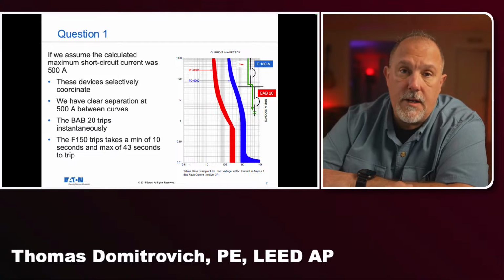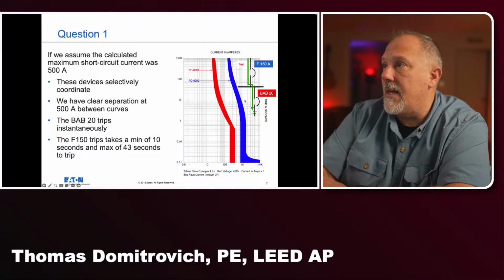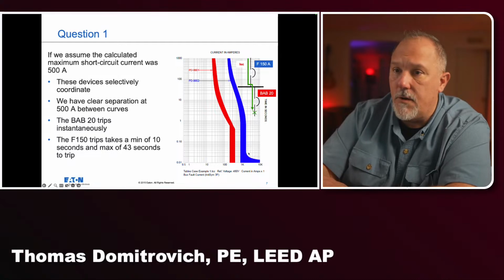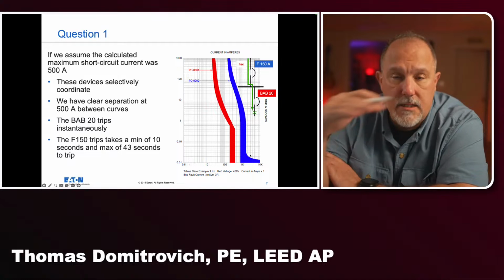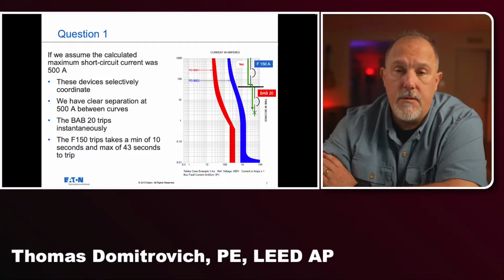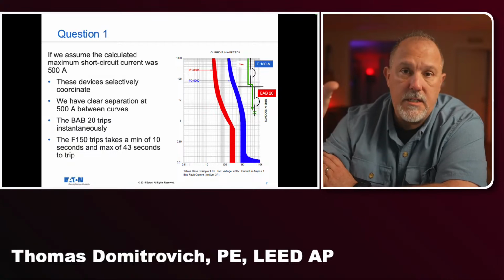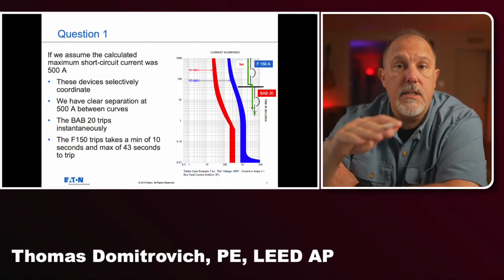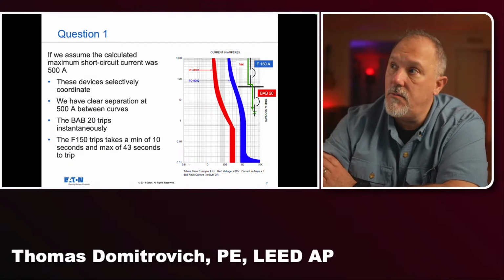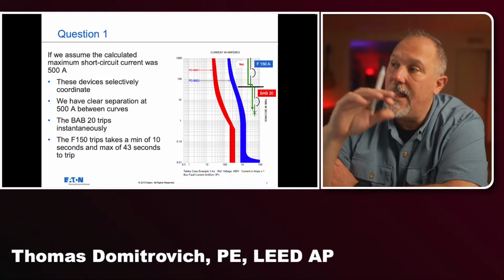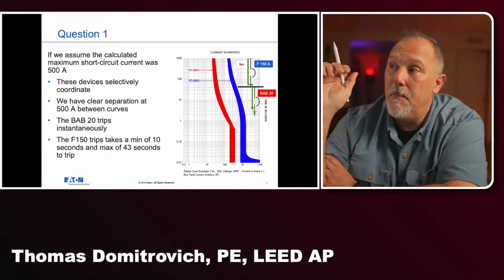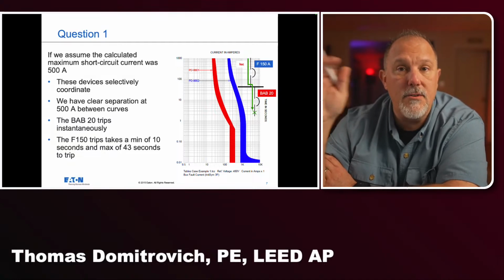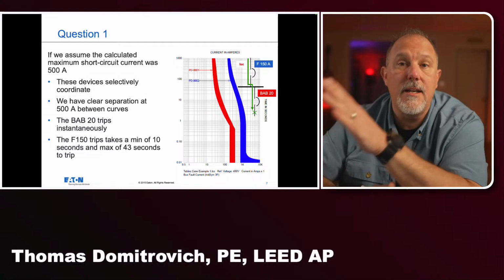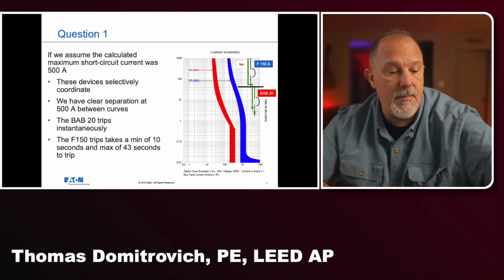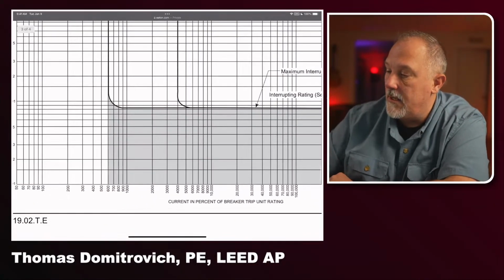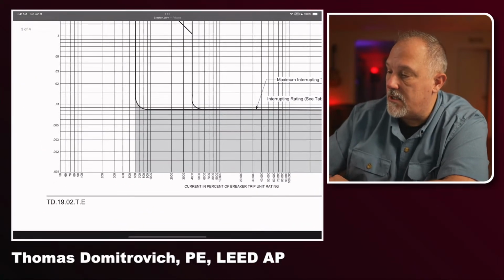So if it was 1500 amps, if it was 3000 amps, if that's 1000, this is 2000, this is 3000 amps is way over here, well into the instantaneous region of that blue curve. So from the TCC curve, I still would not be able to tell you whether or not those two breakers selectively coordinate because I have overlap in that instantaneous region. But that's not even the case here because that BAB breaker's foot is below 0.01 seconds and you're not seeing it. If you download the manufacturer's information, you would see the foot of where it crosses over.